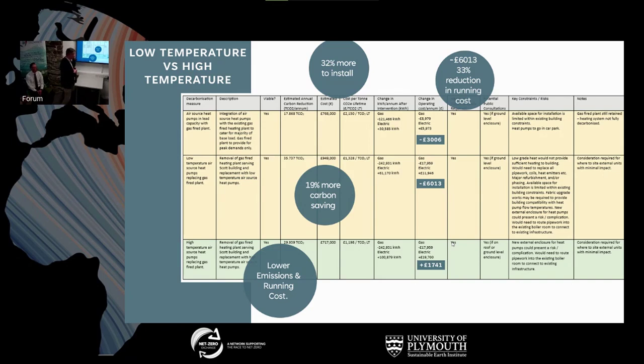This looks like the right solution for that building: lower emissions with a lower temperature solution, lower running costs, 19% more carbon saved if you go to a lower temperature system. But a lower temperature system means you need to change the emitters—bigger radiators or fan coil units, since you've got less hot emitters in effect, so they need to be bigger to get that heat out. So it could cost 32% more to install in this instance, but we get a 33% reduction in running costs—there's a bit of give and take there. If we went for the out and out high temperature heat pump, it would actually cost more to run, and that could change depending on what happens with electricity prices in 2 months, 2 years, or whatever—it can change almost at the flip of a coin.